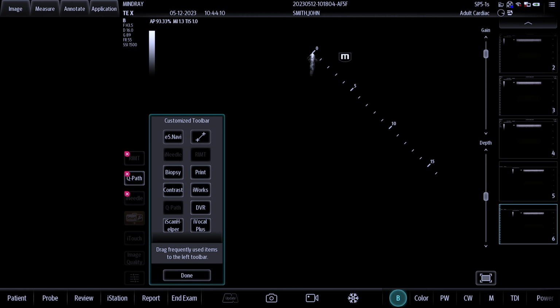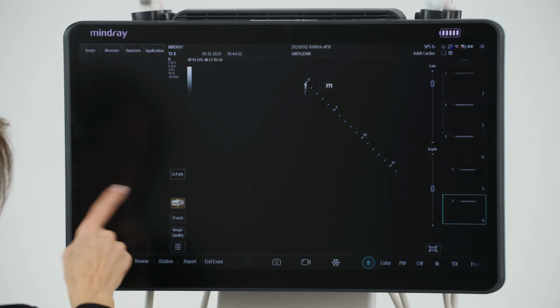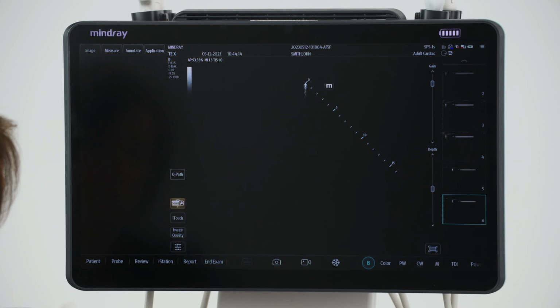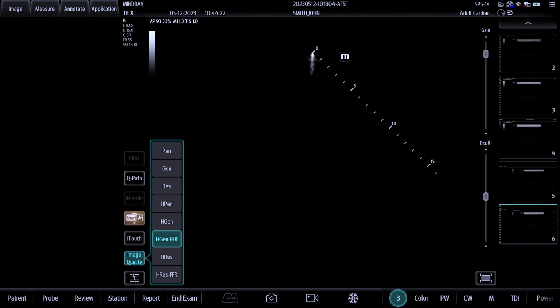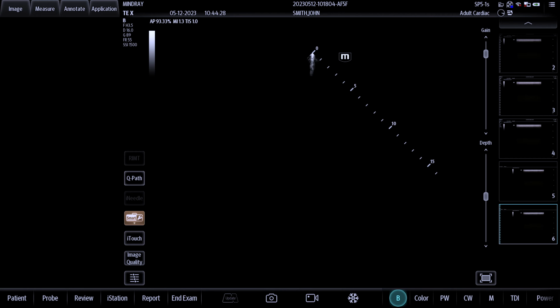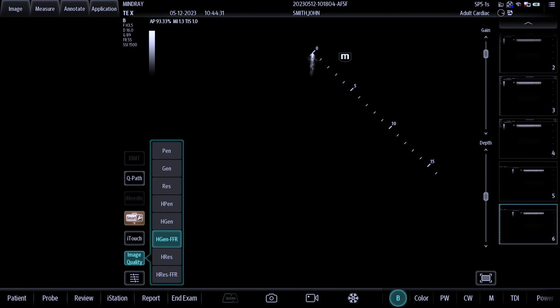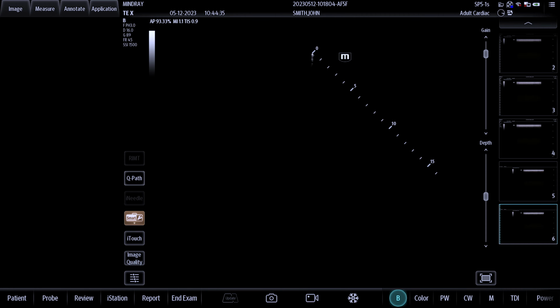There are four customizable slots available above the permanent tabs for the Smart Toolbox, iTouch, Image Quality, and TGC tabs. The IQ key is where the frequency can be adjusted. There are six frequencies to choose from. There are three fundamental frequencies and three harmonic frequencies. Most of the time, the frequency will not need to be changed since the optimal frequency is applied to the exam preset. The iTouch key is the auto gain optimization.